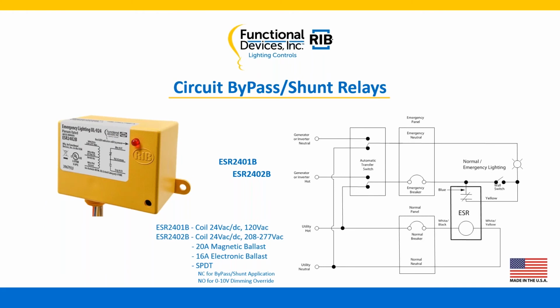From there, these are our actual models. We've got a couple of models of this. We've got an ESR 2401B and an ESR 2402B. Our nomenclature stands for something: the 24 stands for 24 volt AC/DC, the 01 stands for 120 volt AC, and the B is the type of relay we've got. If you look at our second model there, it's an ESR 2402B. It handles the 24 volt AC/DC. It also handles 208 through 277.